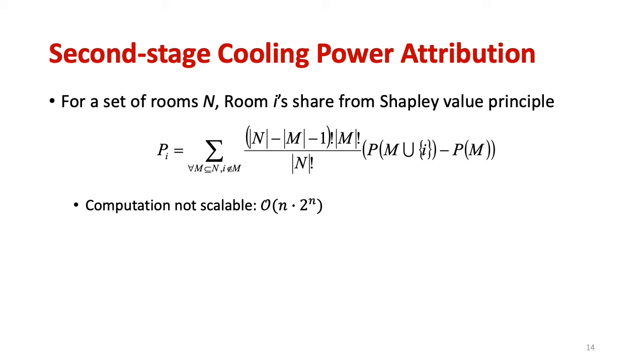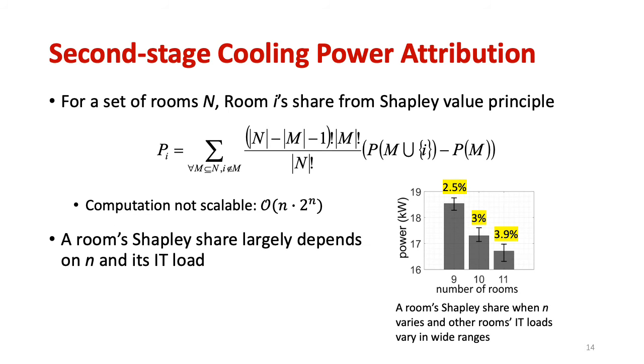For the second stage cooling power attribution, we follow the Shapley value principle for a set of fairness properties. However, the computation of the Shapley value is not scalable with respect to the number of rooms. From our measurements, we find that a room's Shapley share largely depends on the total number of rooms n and the room's IT load. For example, the right picture shows a room's Shapley share when n varies and other rooms' IT loads vary in a wide range. This room's Shapley share only has a few percent variations.